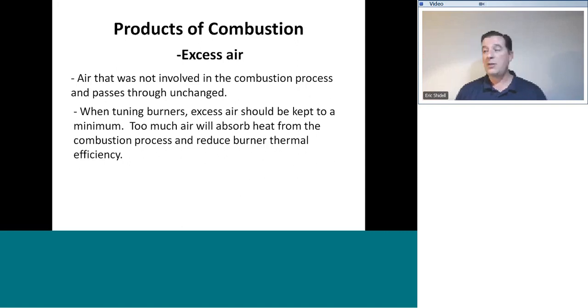That's going to lead to an inefficient operation of our burner. We'll burn nice and cleanly because we'll have more than enough air to burn, but are we getting all the heat value out of that gas and putting it into the water of the boiler or into the air of the forced air furnace? No, we're sending a lot of it up the flue. So we've got to have the right amount of air for combustion, but not too much excess air because that's going to lead to fuel inefficiency and higher operating costs.